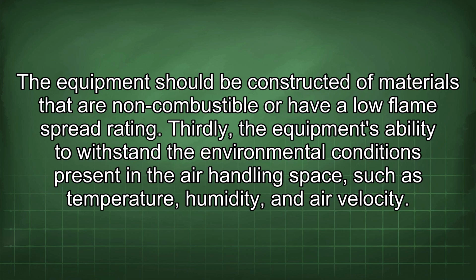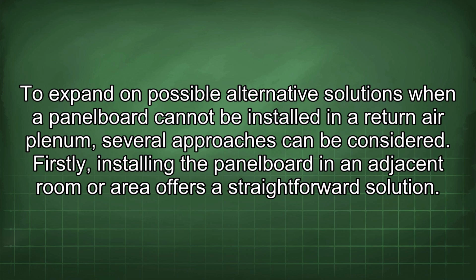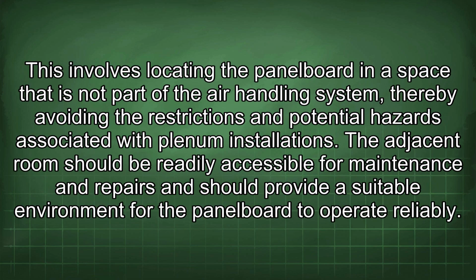To expand on possible alternative solutions when a panel board cannot be installed in a return air plenum, several approaches can be considered. Firstly, installing the panel board in an adjacent room or area offers a straightforward solution. This involves locating the panel board in a space that is not part of the air handling system, thereby avoiding the restrictions and potential hazards associated with plenum installations. The adjacent room should be readily accessible for maintenance and repairs and should provide a suitable environment for the panel board to operate reliably.